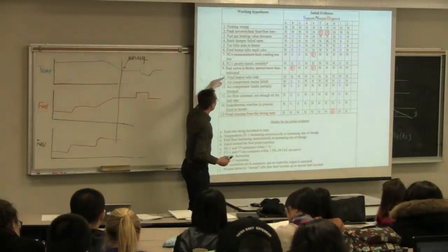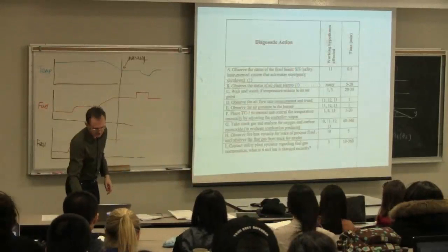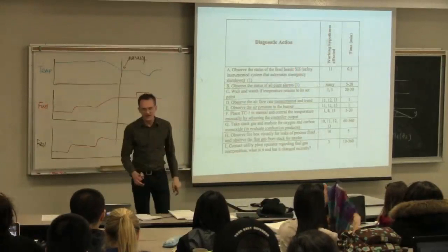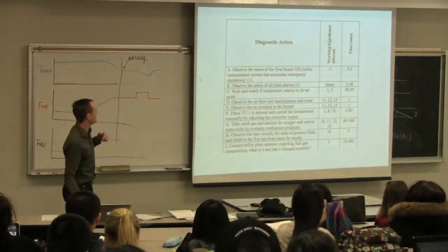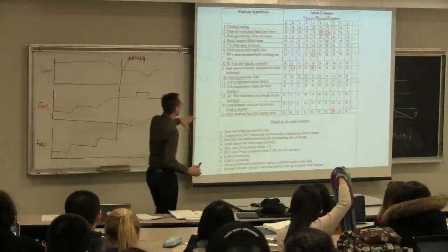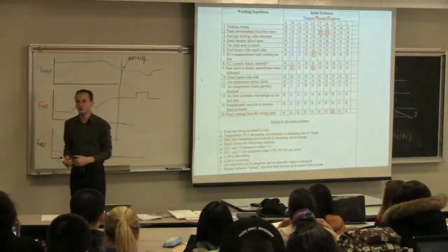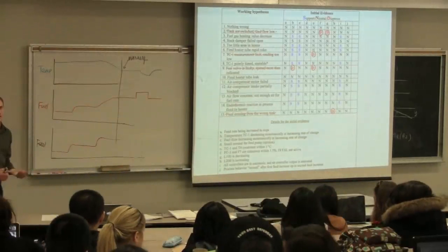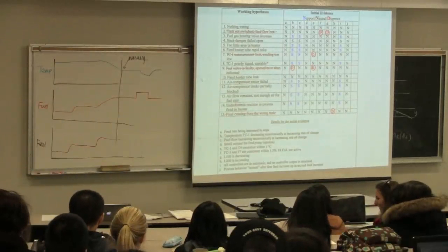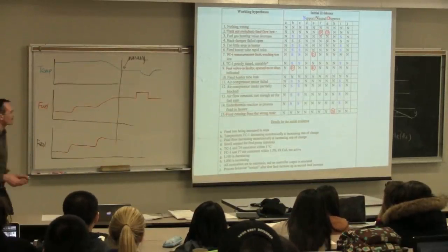By the time we got to this diagnostic test, number 8, we had eliminated several of the possibilities already in the table. The ones that were remaining were mostly related to airflow and fuel flow. So it would become more apparent that making a test to check the fuel flow and airflow ratio would be a suitable way to diagnose this case.